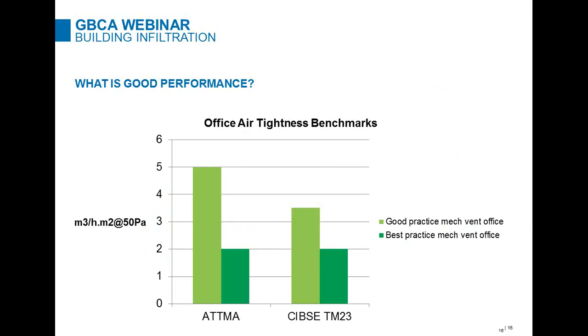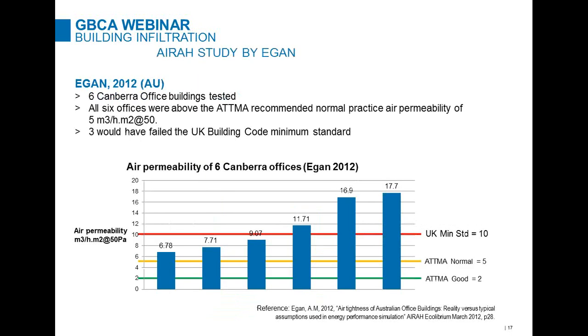A little bit of variance in terms of what good practice is, but somewhere between 3.5 and 5, and probably the minimum standard being 10. So there's only one study in Australia that's looked at commercial building air tightness that I'm aware of, and that was by Egan, published in AIRAH in 2012. And that tested 6 commercial office buildings in Canberra. And what you can see here is the results, the infiltration results, ranging from 6 up to 17.